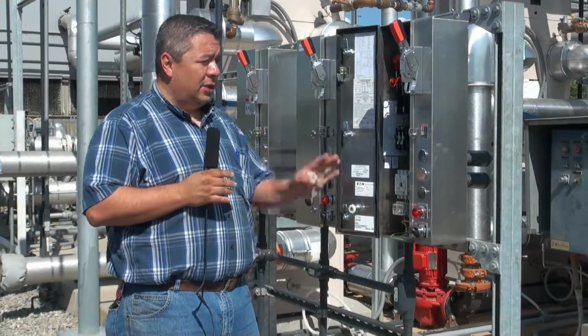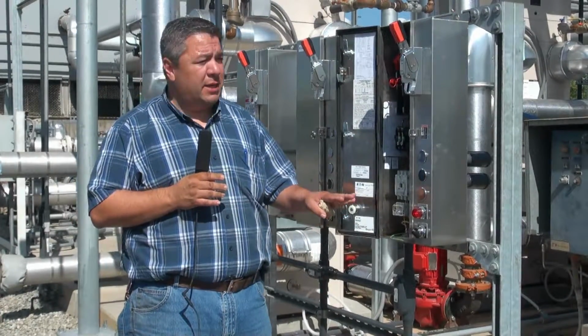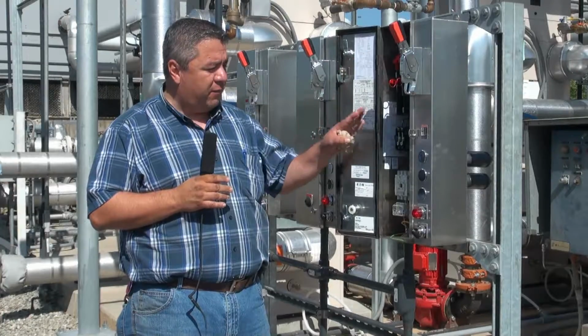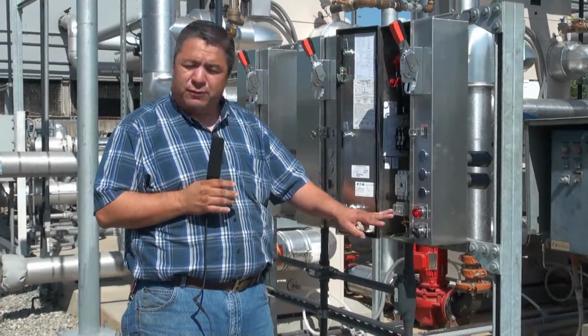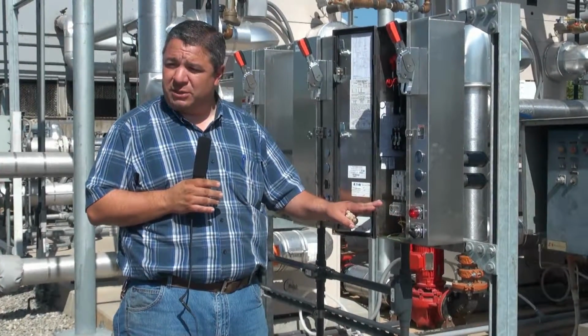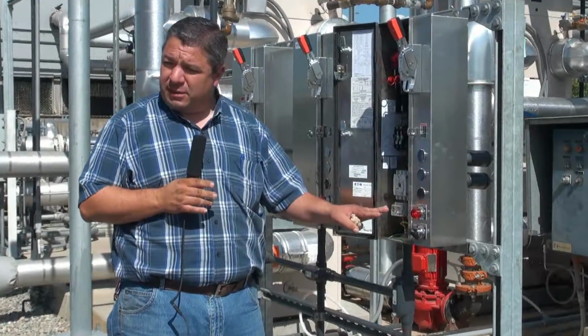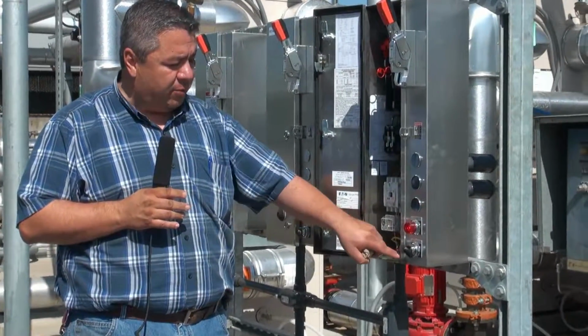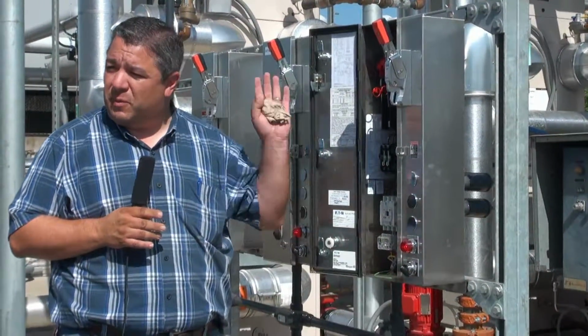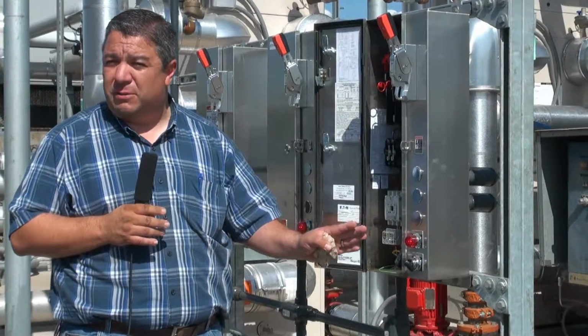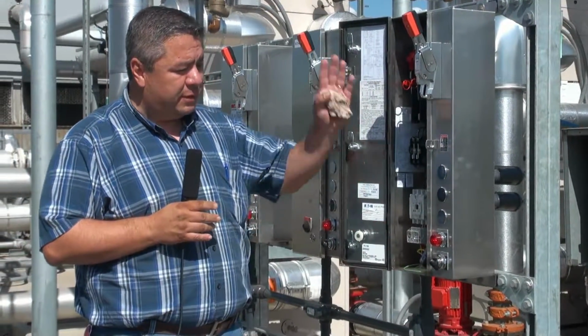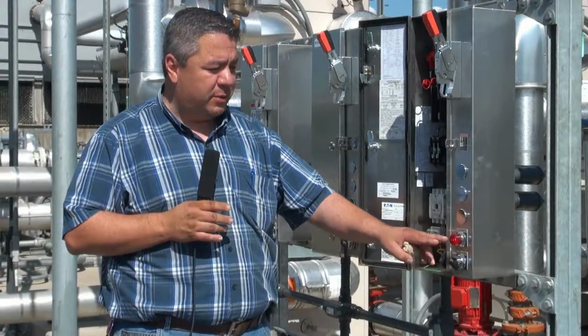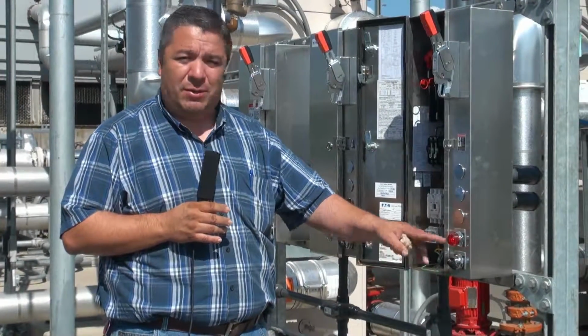Okay, so again, simple disconnect. It's got the three fuses for the high, for the low. It's got the mag starter. It's got the overload protection with the overload protection knob set. It's got the test buttons for it, and it's got the relay for the automation because once the command sends for the boiler to come on, it turns the pumps on. Stainless steel container. It's got a hand-off-auto switch with the light. You can't see it in the sunlight, but it does turn on whenever the pump's on.